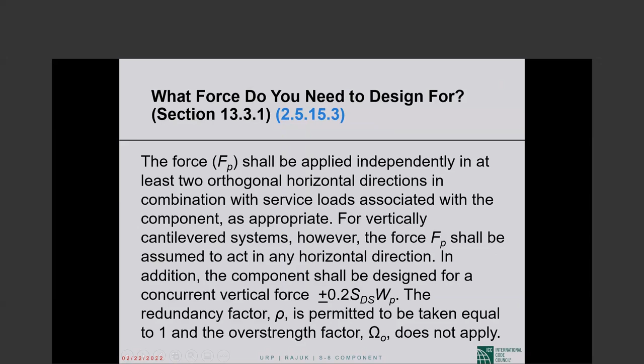For vertically cantilevered systems, the force F sub P shall be assumed to act in any horizontal direction. In addition, the component shall be designed for a concurrent vertical force of plus or minus 0.2 S sub ds times the weight of the component. Okay, this can be plus or minus. This is on top of the lateral force, the F sub P. It's a vertical force. The redundancy factor rho is permitted to be taken equal to 1, and the overstrength factor omega sub 0 does not apply. Okay. So read this and keep this in mind.